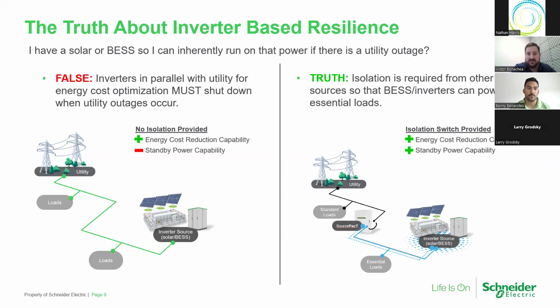If your inverter is operating grid tie and there is a blackout, it has to shut down when it detects that blackout, that brownout, whenever it detects the utility source it's synced to is unacceptable, to prevent the backfeeding and to protect line workers. If you look at the left-hand side here, you see an example of a system without isolation that does have an inverter source on it, and you'll get energy cost optimization out of it when it's working grid tie. But if utility fails and that inverter turned back on, it would backfeed back up to the utility, as you see. For that reason, that standard and that requirement exist. It cannot be used in that case for standby power applications without that proper isolation.